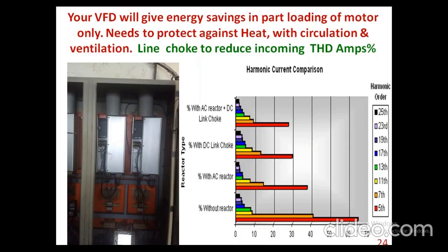The heat sink may be there, a bigger heat sink may be there, the OEM has given, but still the heat cannot go out if the fluff is getting deposited on all the heat sinks. So see to it that the VFD panels and these machines are all ventilated adequately. Coming to the harmonic aspects, all the VFD OEMs always say we have provided a DC link choke that will take care of the system. Definitely it is not. The DC link choke can only give a partial reduction of H5 or H7.